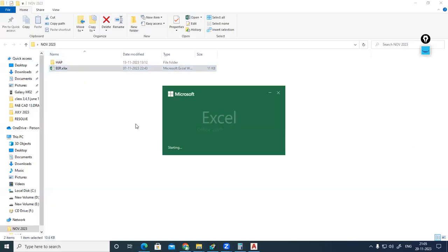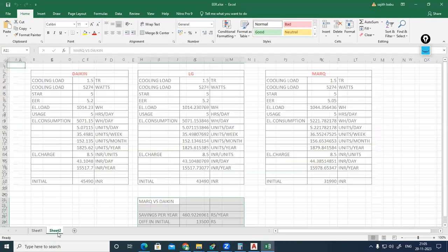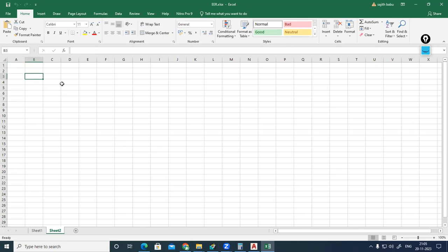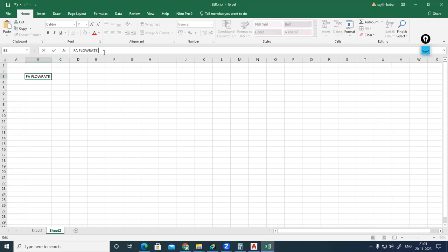See, the total fresh air demand within the space, or total fresh air flow rate or outside air flow rate, will be a summation of people ventilation flow rate plus area ventilation flow rate. We can manually calculate like this. Means each person, how much quantity of fresh air has to be provided inside, plus each meter square of area, how much we have to provide. Accordingly, we have to calculate it.